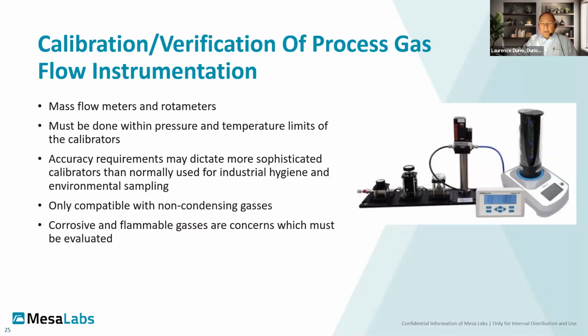I get inquiries fairly regularly, had one last week where they were looking at using hydrogen fluoride. They were unable to tell me whether it was wet HF or dry HF, but my advice to them was they have to accept the fact that with these corrosive gases, they may have to accept a short calibrator life and equipment life, but it has to be addressed and assessed individually.